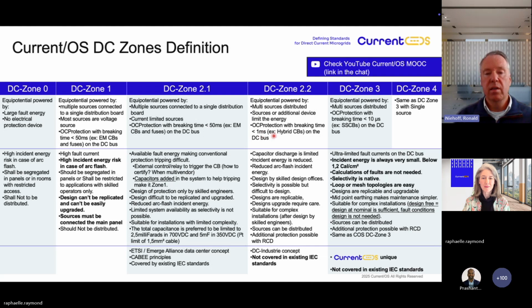There is the area where hybrid circuit breakers are situated with a disconnection time in a fault situation of less than 1 millisecond. Disconnection time is already that low that this is pretty safe. But if you go to DC zone 3 and 4, the breaking time is less than 10 microseconds. And that is the area where only semiconductor solid state circuit breakers, not hybrid, are given with the disconnection time less than 10 microseconds. And you can connect many of such sources with overcurrent protection devices with less than 10 microseconds in such zones connected to the same cable.